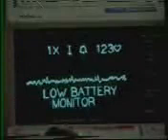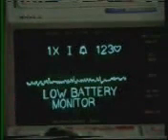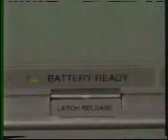The ZOLL 2000 system can be operated by either battery power or plugged into a regular AC wall outlet. If the battery is low, a low battery message will be displayed and a tone will sound. If that happens, the ZOLL PD 2000 should immediately be plugged into a regular wall outlet. The ZOLL PD 2000 can operate for about an hour on battery power if the battery is fully charged. If the ZOLL PD 2000 loses power or will not function in an emergency situation, CPR must be performed while the difficulty is resolved or another ZOLL defibrillator is obtained.